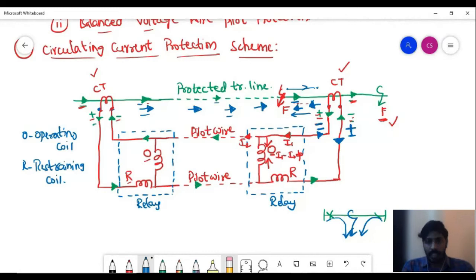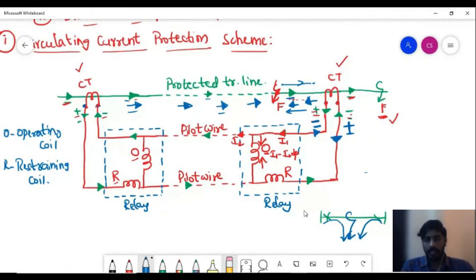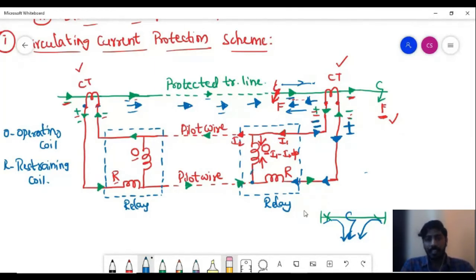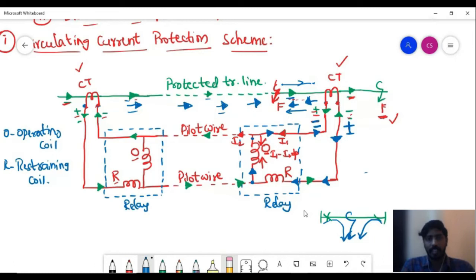The blue color arrows indicate the direction of fault current during fault conditions. Now the current from the sending end CT flows in one direction, and the reversed current from the receiving end CT is added to it, so the currents combine and flow through the operating coil. This is because when the remote end CT polarity reverses, the currents no longer circulate through the pilot wire but instead add up and drive current through the operating coil.